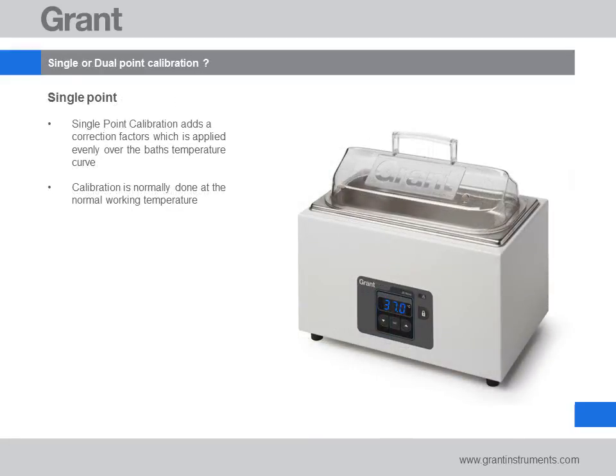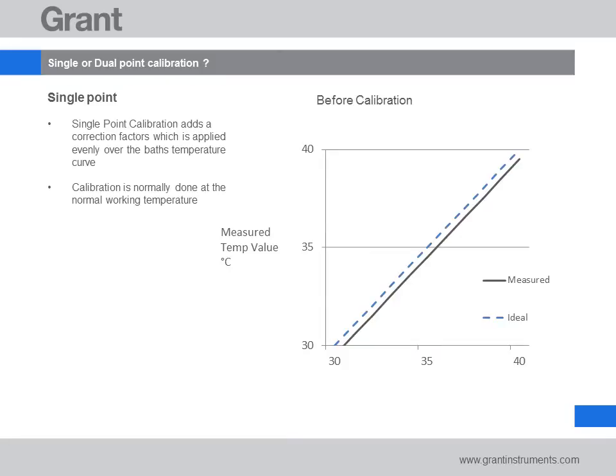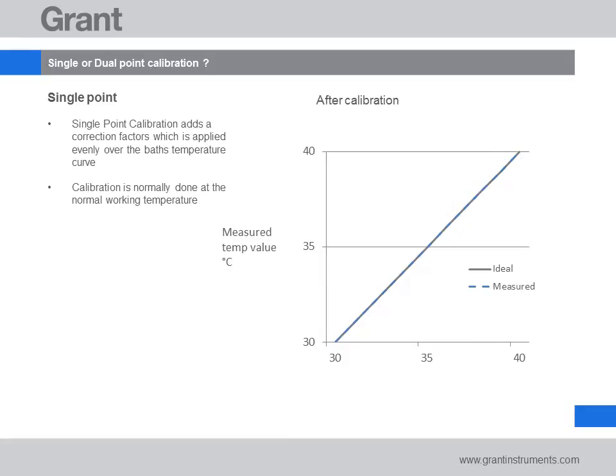Deciding on a calibration method is simple. Single point calibration, which is available on all water bath models, allows a correction factor to be applied evenly over the bath temperature curve. We'd recommend that for optimum accuracy you calibrate at a commonly used temperature for your work.